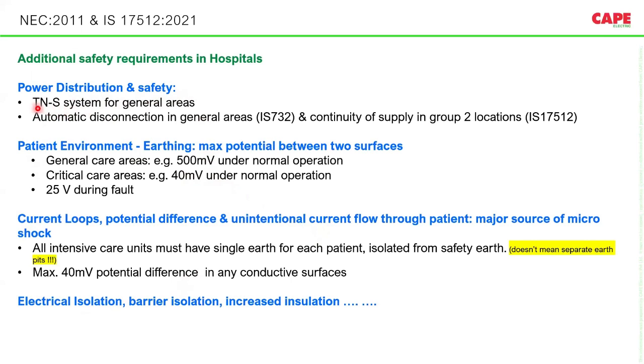Power distribution and safety. First of all, the system earthing must be TN-S for general areas, and automatic disconnection in general areas is a safety measure. Continuity of supply in group 2 locations as per IS 17512. Of course, the NEC, National Electrical Code, also explains both these requirements.